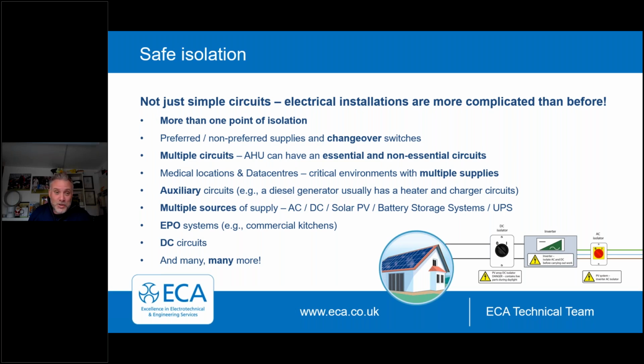We said medical locations and data centers are critical environments, so they have multiple supplies. They're designed never to be isolated, so they might have multiple supplies that you'll need to identify and switch out. You might have auxiliary circuits, so if you're working on plant and equipment and generators, they may have auxiliary heater and charger circuits, which is important that we do remove all sources of energy, just not the primary. We've got a little diagram down here of a solar PV system. So many homes and businesses at the moment are taking advantage of producing their own energy. There's multiple sources of supply there. There is AC, DC, solar, battery backup, UPS. So again, it may be more than one point of isolation.